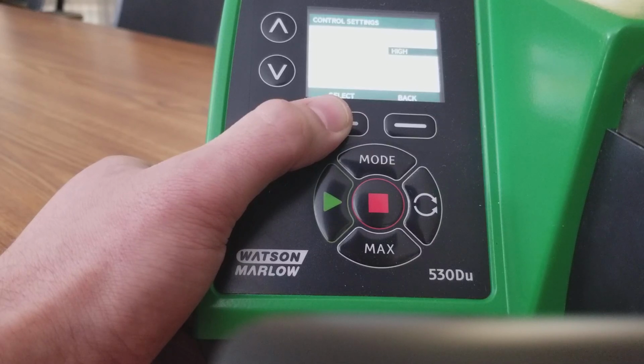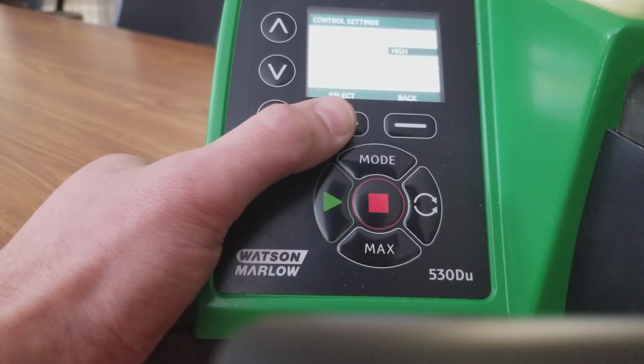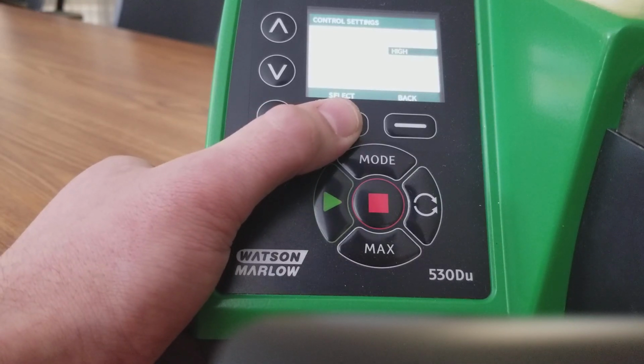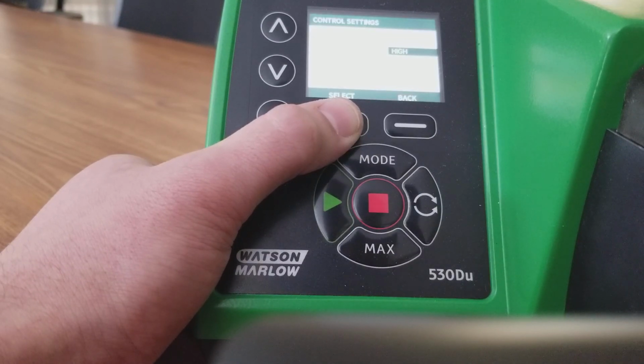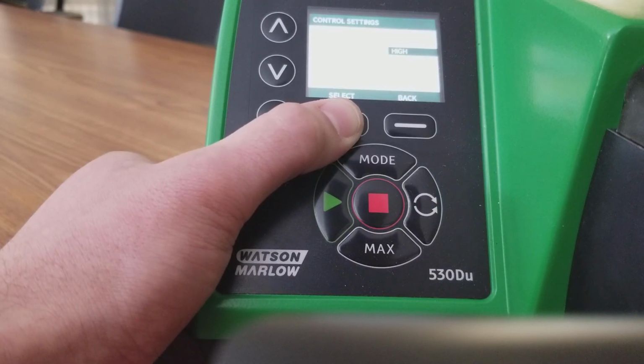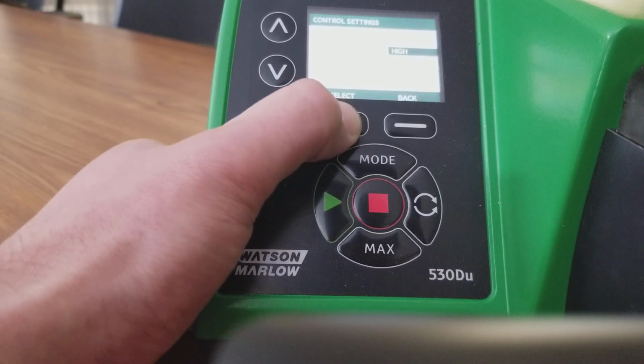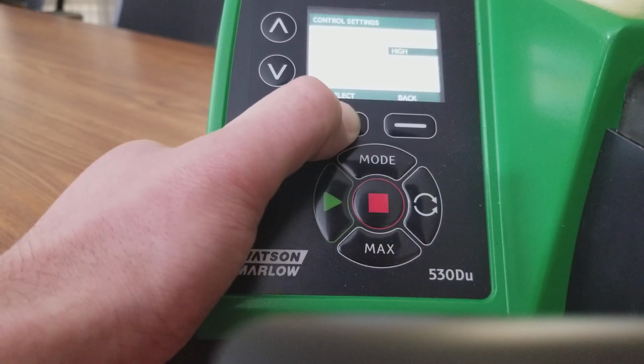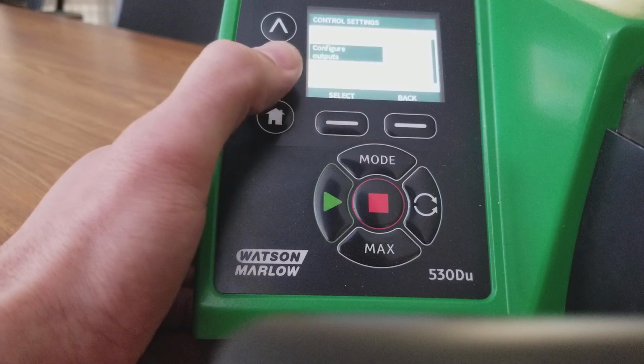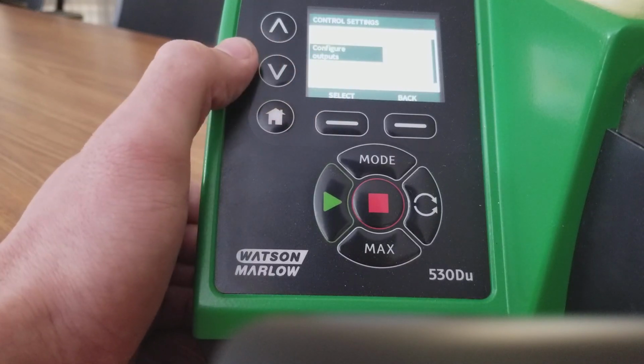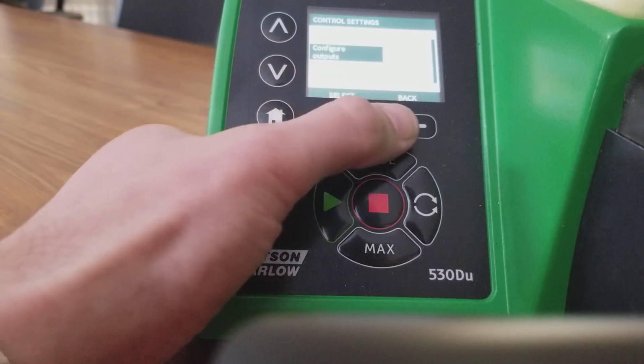The high and low is basically the exact same as normally open or normally closed. On most situations I've seen that high is selected. If you're always getting an alarm, then you would go back into this feature and select low to make sure that it would operate properly. So for this, we'll just select high. We'll assume that there was only one input on a relay and move on.